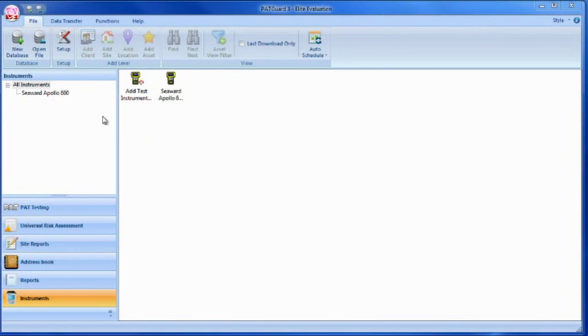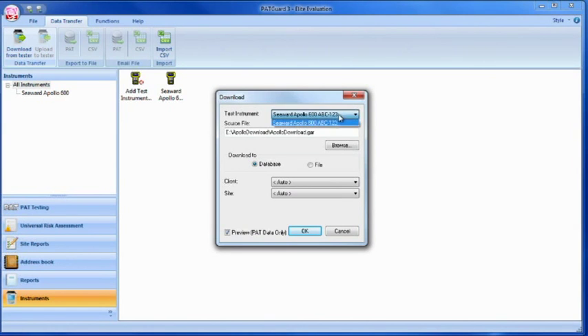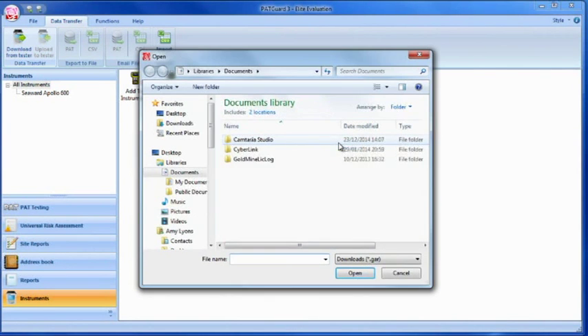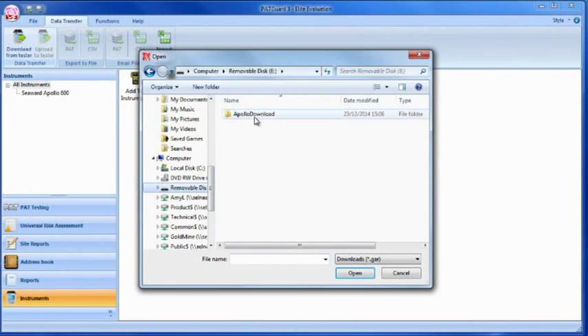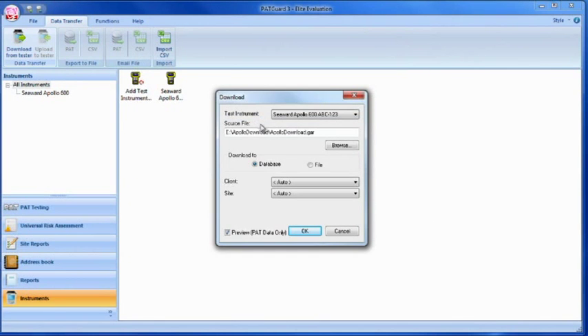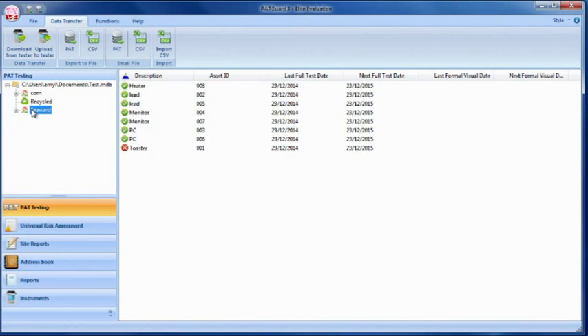Select Data Transfer and Download From Tester. If you receive a message saying 'Error: Unable to detect an available COM port', click to accept. Select the instrument from the drop-down box and browse for the .gar file on the flash memory stick. Select Open and then OK. Your downloaded data should appear in the PATGuard 3 database.